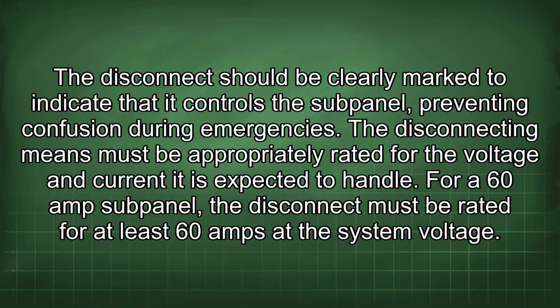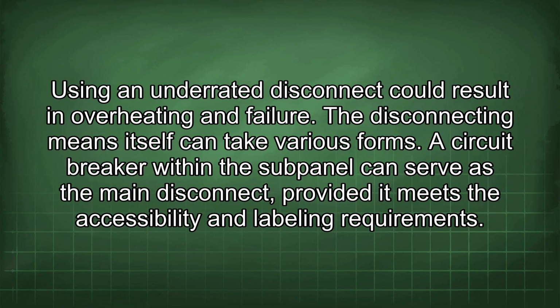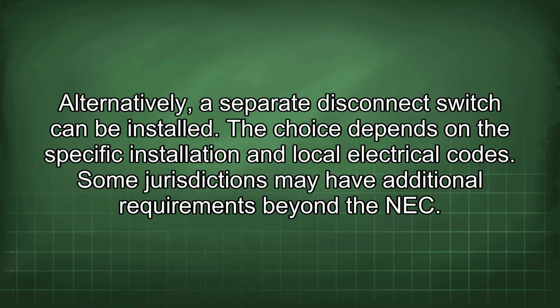The disconnecting means must be appropriately rated for the voltage and current it is expected to handle. For a 60 amp subpanel, the disconnect must be rated for at least 60 amps at the system voltage. Using an underrated disconnect could result in overheating and failure. The disconnecting means itself can take various forms. A circuit breaker within the subpanel can serve as the main disconnect, provided it meets the accessibility and labeling requirements. Alternatively, a separate disconnect switch can be installed. The choice depends on the specific installation and local electrical codes.